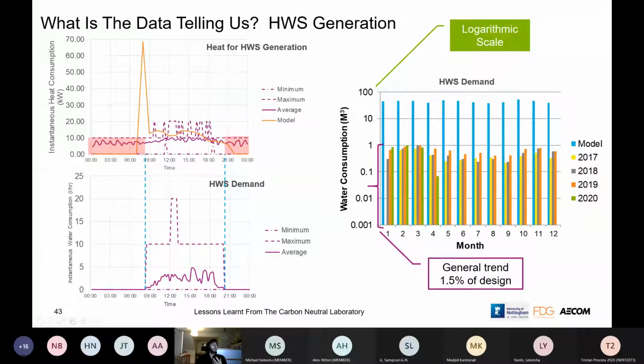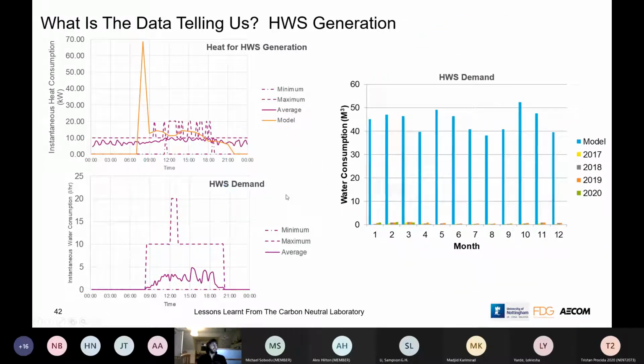Which is really important because it shows that maybe things like local hot water generation using electric resistive heating, normally not that efficient, actually on aggregate is far more efficient, because we don't have the losses associated with pumping all this hot water around the building.